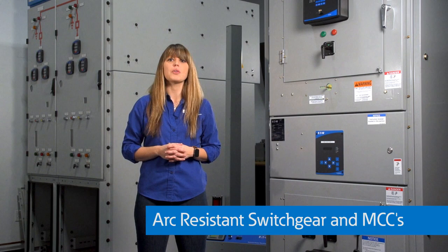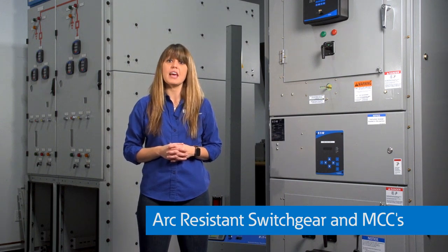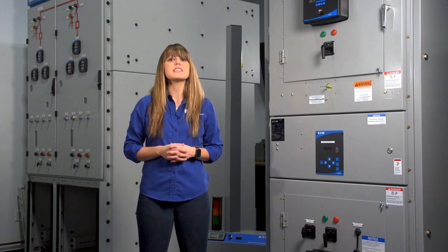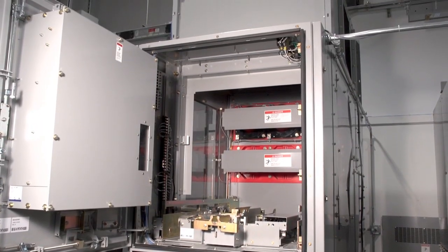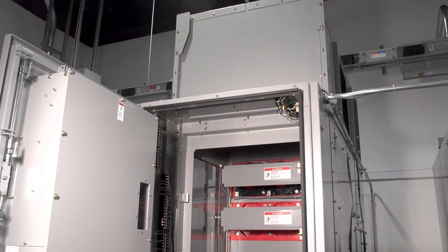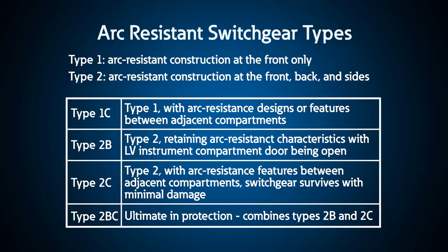The first solution is called arc-resistant switchgear and MCCs. In general, arc-resistant equipment contains and redirects arc energy away from personnel and the facility out of the top of the equipment.